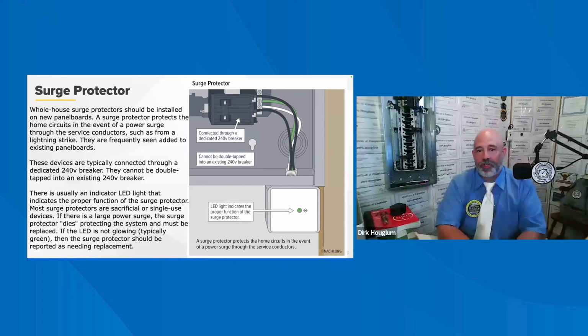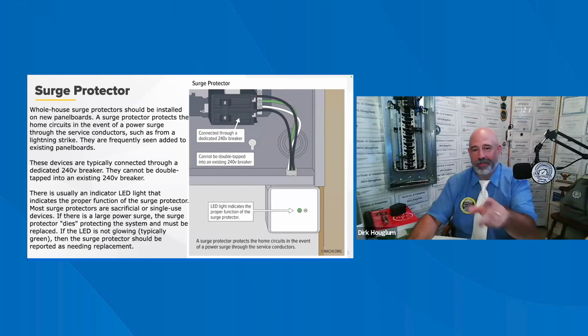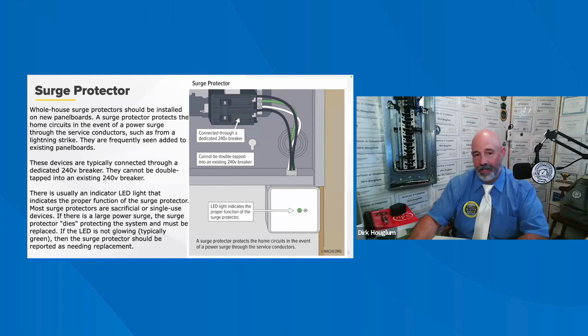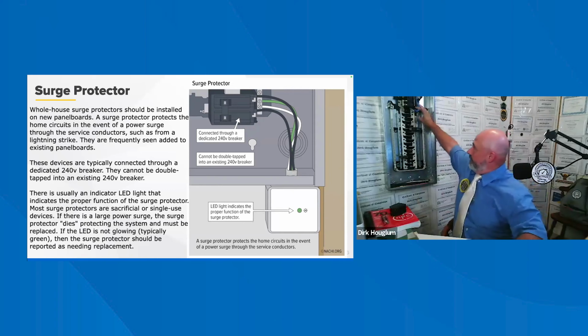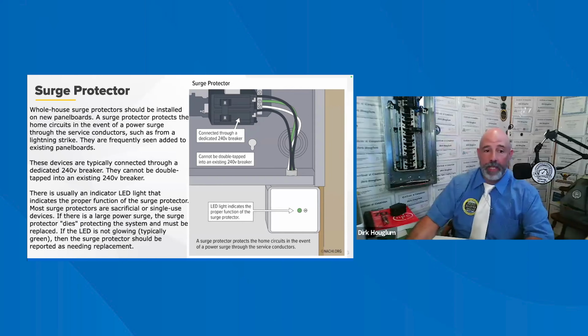All right, surge protectors. Now, in NEC 2002, article 285, surge protectors or surge suppressors are mentioned. In 2020, article 230.67 says it is a mandatory requirement for the first time for dwelling units to be provided with a Type 1 or Type 2 SPD, service protector, okay, or surge protective device. So that's it. Normally there's a little light on there and you can see that it's on. Now they have them more inside the panel. They actually snap in here and they should not be double tapped.